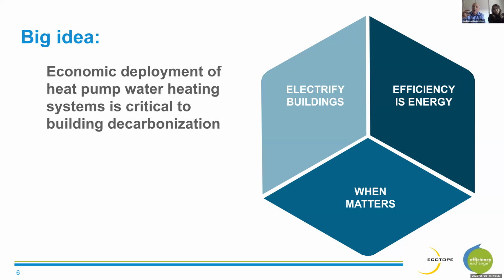And so this project at Bayview Tower really brings together all 3 of those responses to the climate crisis by replacing the water heating system, because it's an example of electrification of water heating. It's a super efficient way to do that, and it allows us to shift the time of when we use that electricity off of the grid peak periods.